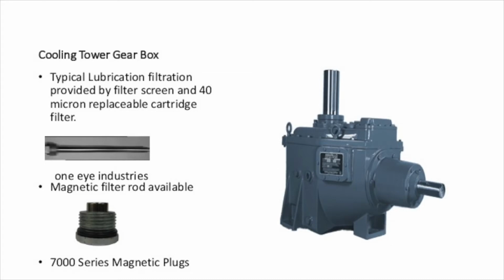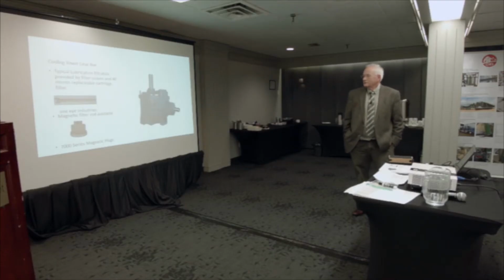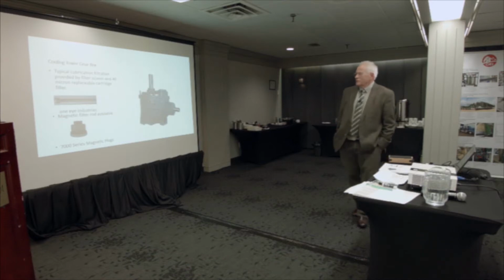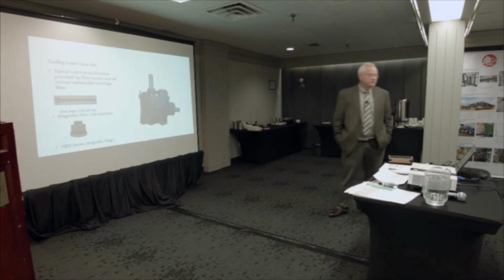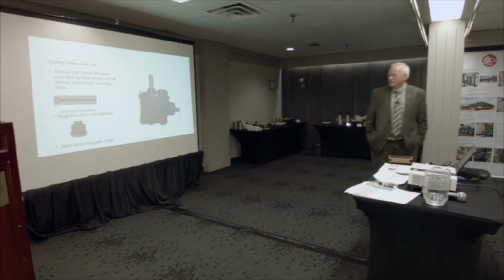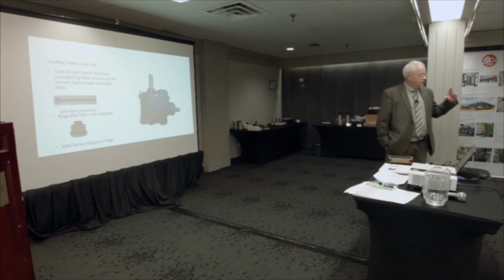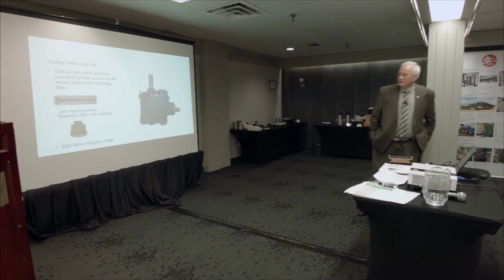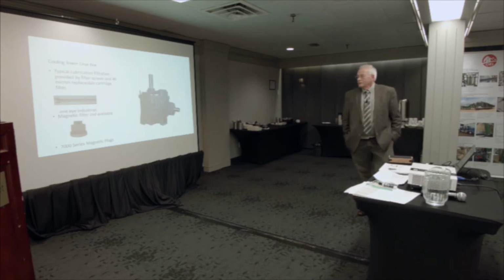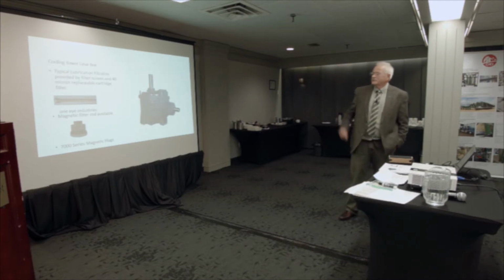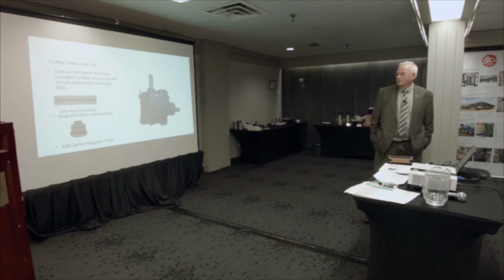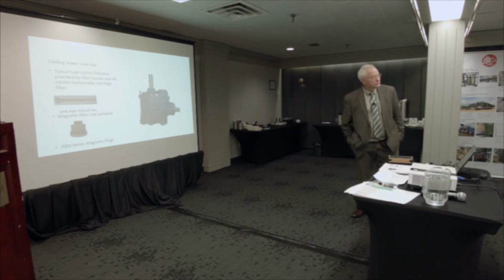Cooling tower gearboxes. We had a lot of failures when we first started bringing the cooling towers into the cogeneration business in Ontario, our first 2 plants. And basically, failure of the gearboxes, and a lot of it was due to contamination of the gears. And just simple, they just have a small, I don't know, like 30 or 40 micron screen in there, and obviously not enough to protect the engine or to protect the gearbox. And when these fail, typically they take the fan out, the whole works. There's a lot of damage, and you're looking at easily $500,000 to replace one of those.